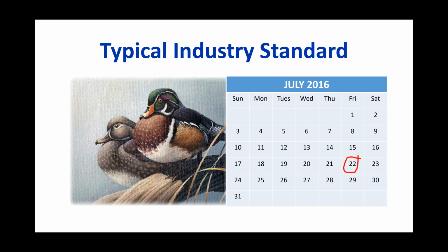Now, for most, the standard process for filter changes in various facilities has been a few things. One, like the calendar, is based on time, either of calendar days or tracking the runtime of the equipment. We also sometimes see visual inspection, and on a rare case, pressure differential using magnehelic gauges or through a BAS system.